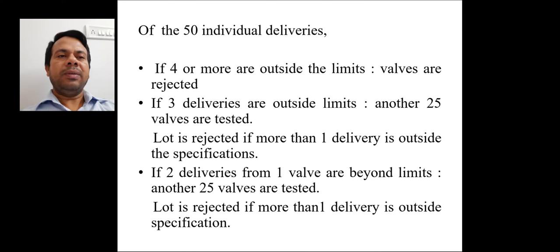If 3 deliveries are outside the limits then another 25 valves are tested, and the lot is rejected if more than 1 delivery is outside the specification. If 2 deliveries from 1 valve are beyond limits then another 25 valves are tested, and the lot is rejected if more than 1 delivery is outside the specification.